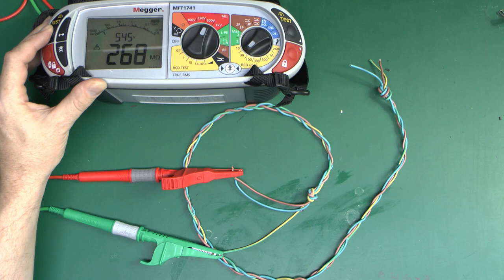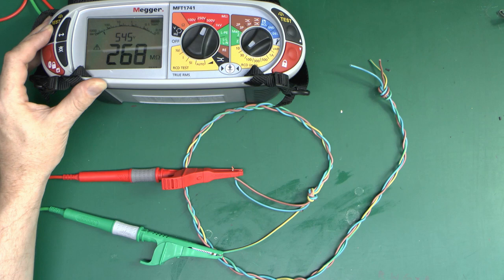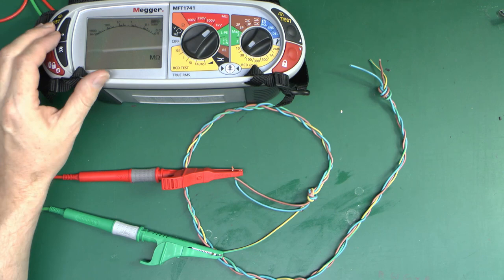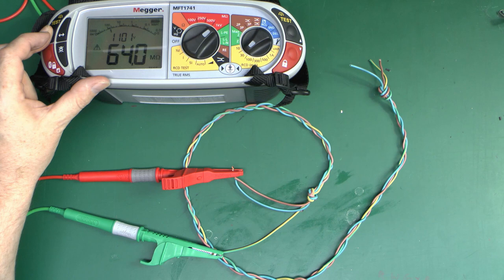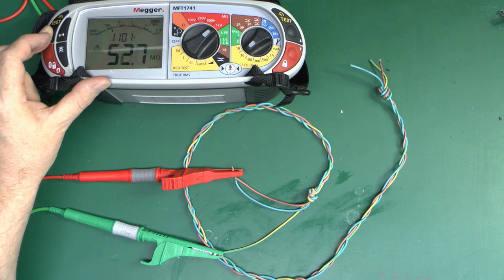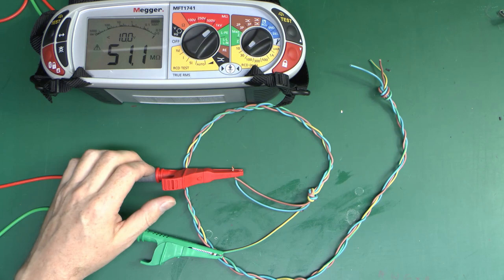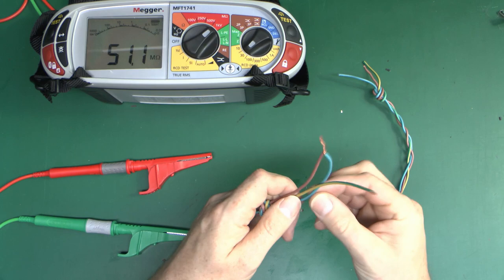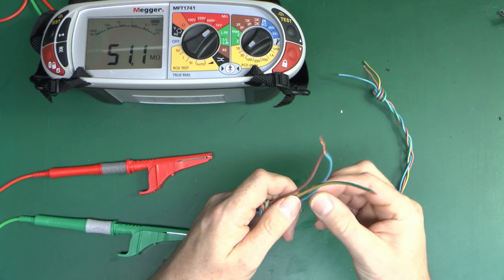Let's try the 1000V test anyway, just as well. You know that warning there, because obviously putting 1000V in your fingers is not desirable. And yeah it's the same pattern again, it's actually more severe this time. Starts out in the 100 plus and there it is falling away already below 600 megohms. And if we keep the voltage on for a long time, as you can see it's still falling away at quite a rate. So yeah, definitely the insulation in this cable. I'd say it looks perfectly fine, but pretty obviously it definitely is not. So there we go.